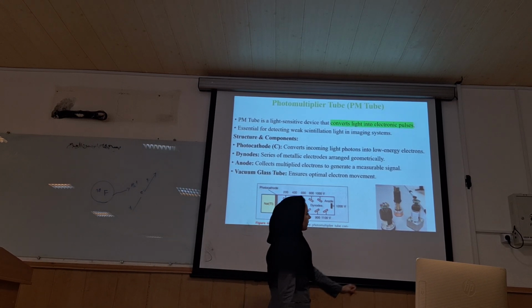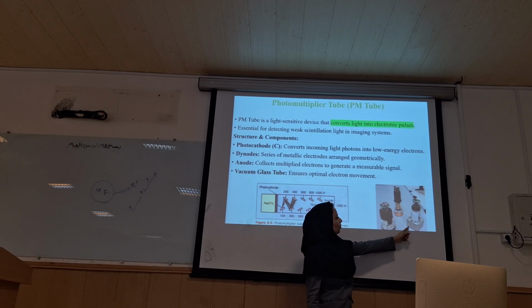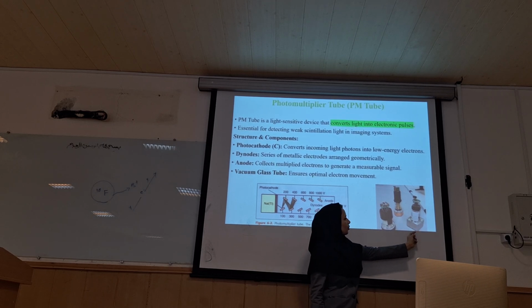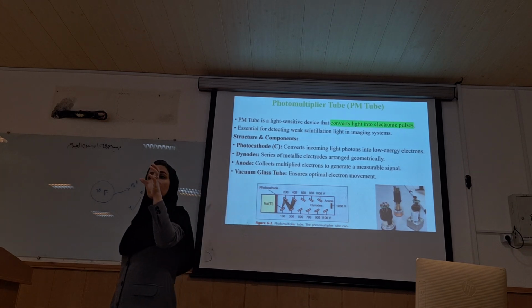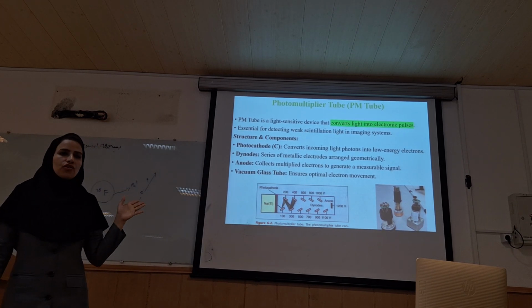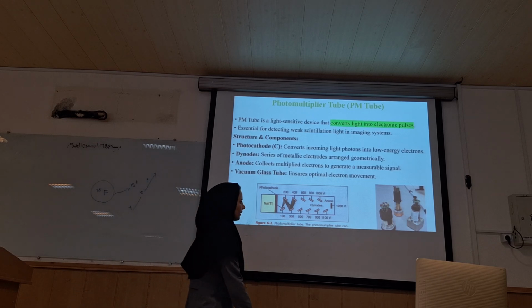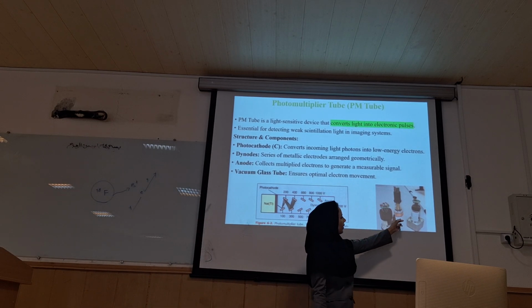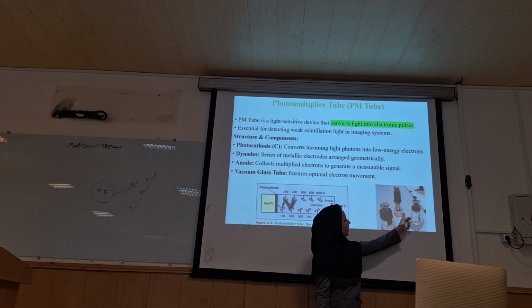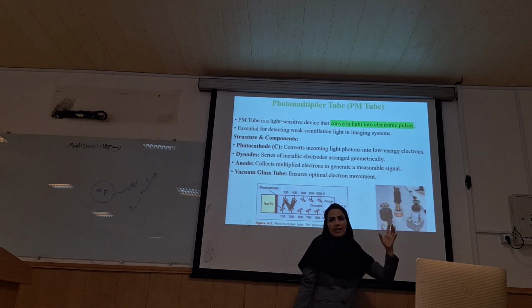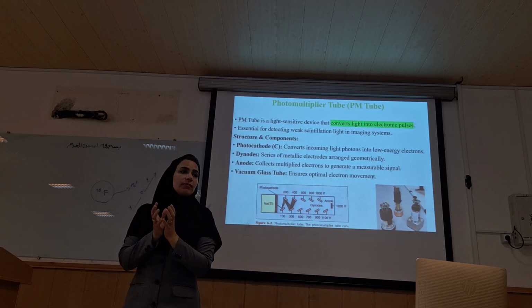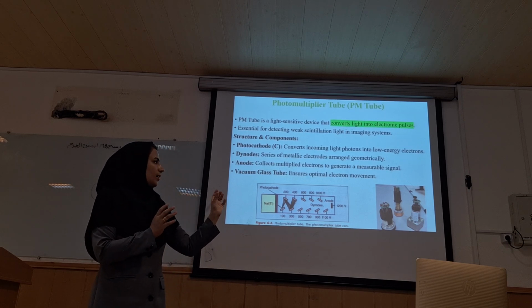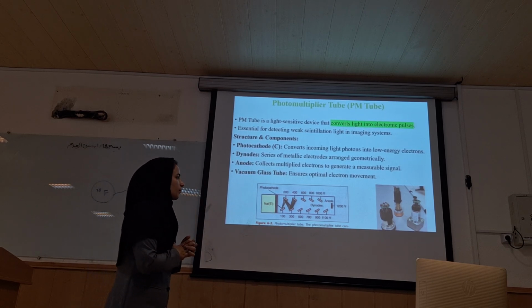We have different shapes of the photomultiplier tube. For example, this is the cube, this is the hexagonal, and this is the circular, depending on the company, and each of them can be used. But overall, when we use the hexagonal, this is important because we have a good matching between the PM tubes when we use the hexagonal. This is important.